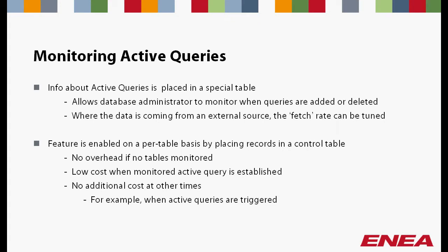A more recent extension to the active query mechanism has already proven very useful in certain SCADA applications. If, for example, a number of remote sensors are connected in via cellular network technology, then it may be impractical or expensive to keep all the connections open all the time, and instead one could adopt the strategy of polling individual points infrequently. If an operator wants to monitor a particular sensor in real time, this latest extension means it's now possible for a helper application outside the database to detect when an active query is started on such a sensor's record. The helper application can then ensure the sensor is polled more frequently while the active query is open, and drop the polling frequency back down again to its normal value when the active query is terminated.